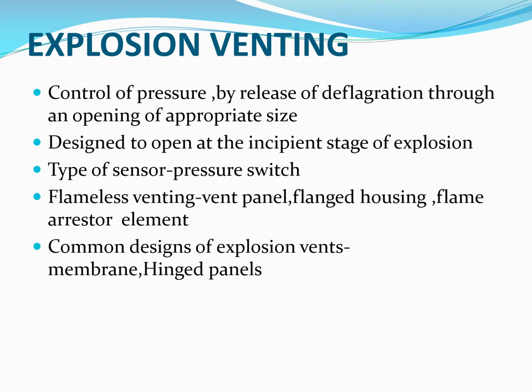Common designs of explosion vents include a membrane type, where a membrane breaks at a preset pressure to allow the flame front to exit, used in high-pressure situations. Another type is a hinged panel, where a spring-loaded hinged panel opens at a preset pressure to allow the flame front to exit the system. The advantages of explosion venting systems are that they are relatively inexpensive compared to other explosion protection options and are simple to install.